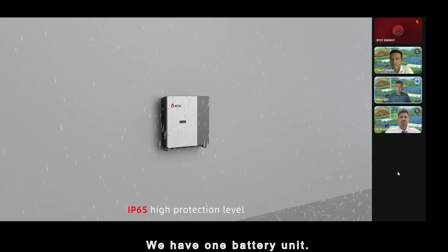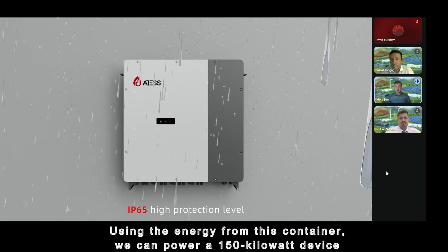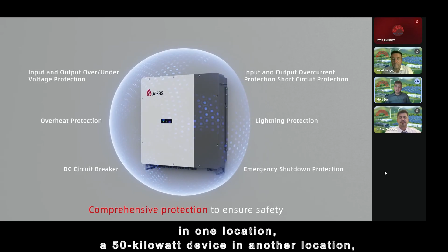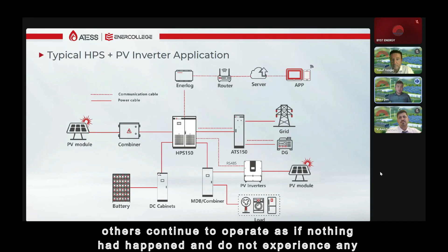What I mean is this: we have one battery unit, a container that can be installed anywhere. Using the energy from this container, we can power a 150 kilowatt device in one location, a 50 kilowatt device in another, and various devices ranging from 30 kilowatts, all without them being connected in parallel, ensuring seamless operation. Even if one device malfunctions, the others continue to operate as if nothing happened, with no issues to their own critical functions. In other words, by using a central storage unit instead of a central inverter, we have resolved this issue.